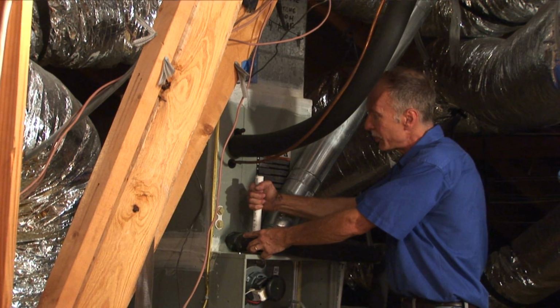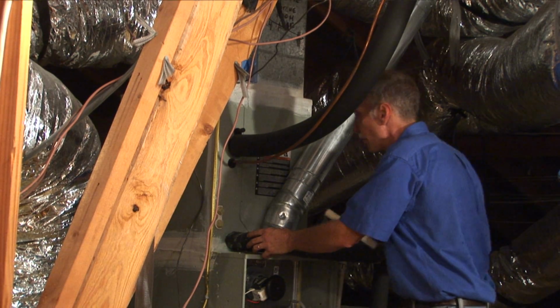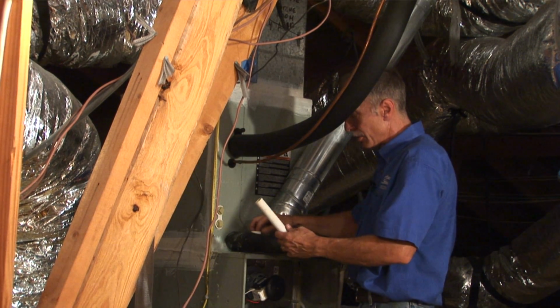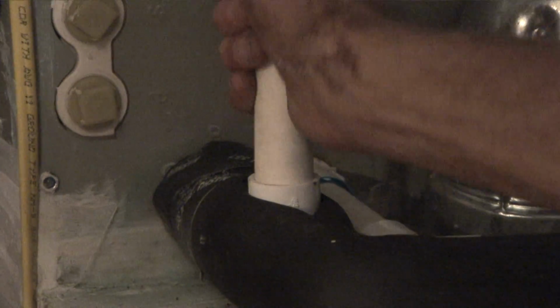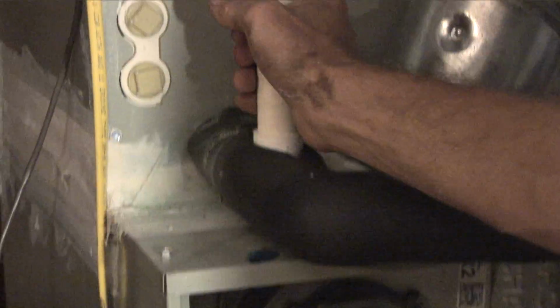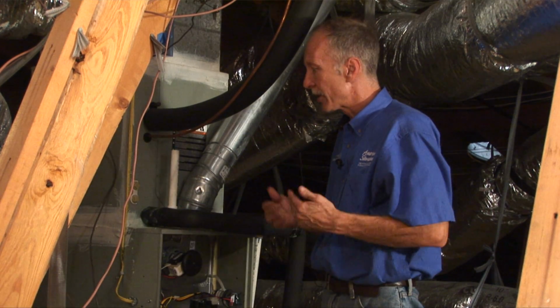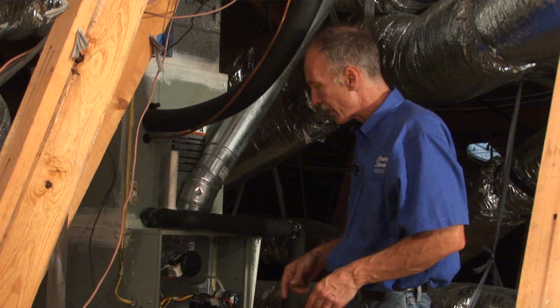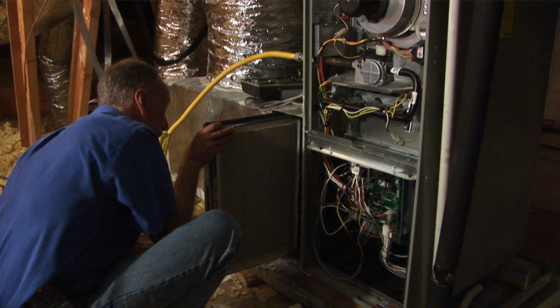The next is a visual inspection of the drain lines. What we can do is we can remove this tube and we can look inside here and make sure that all of the water is flowing freely and that there's no buildup. So that's it. The only thing left is to go ahead and get these filters reinserted, get the doors buttoned back up, and then we're done.